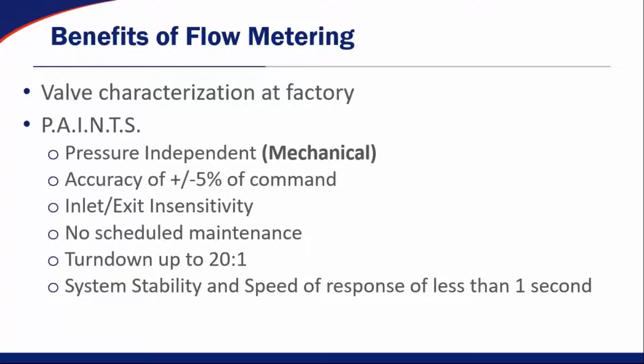There's no scheduled maintenance on the Phoenix Controls valve because there are no parts inside the airstream that will get clogged up and dirtied having to do with the control of the valve. We have a large turndown ratio up to 20:1, which is much greater than flow measurement devices have, and we guarantee the best system stability and speed of response to less than 1 second.